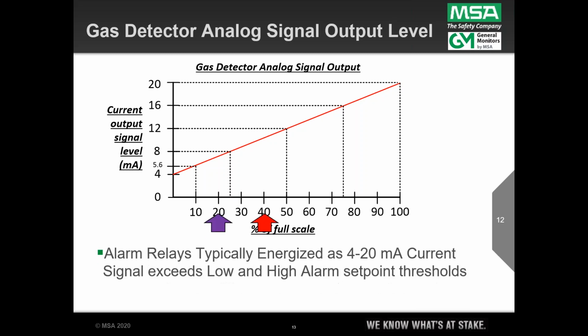Super easy to understand, and the logic solver will normally have threshold settings at 20% of scale and 40% of scale to equal a low alarm annunciation device like a light, and then at 40% a high alarm annunciation device like a strobe or a horn, and our logic solver would energize those guys.